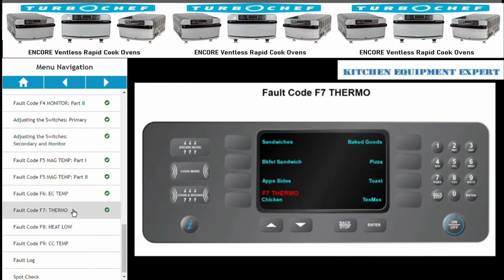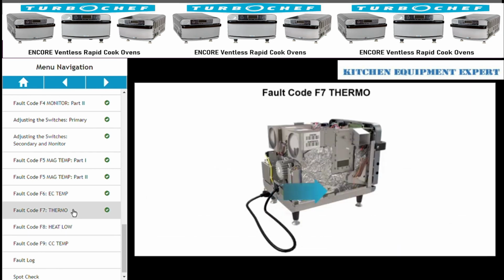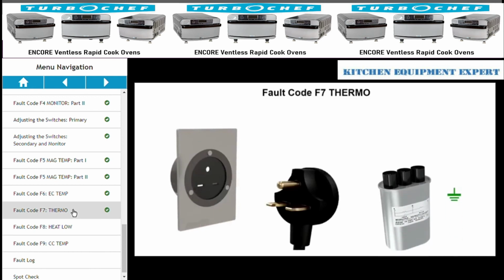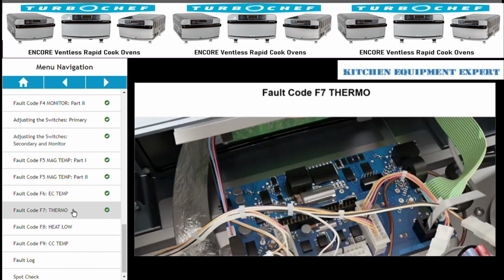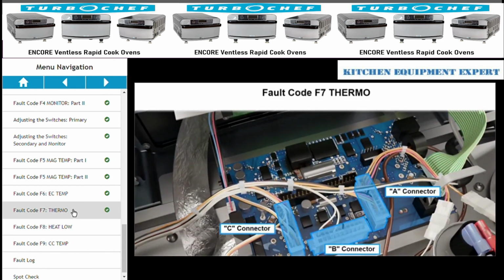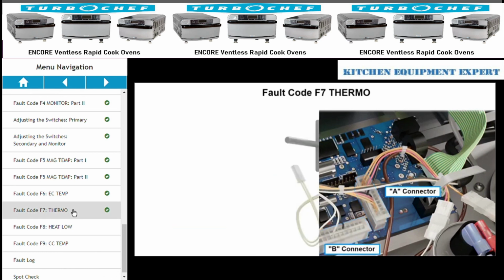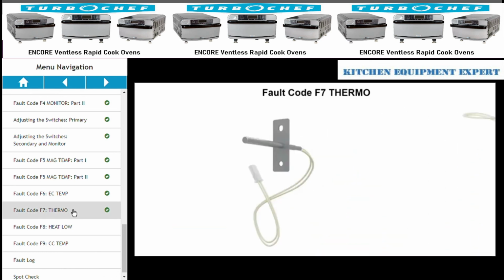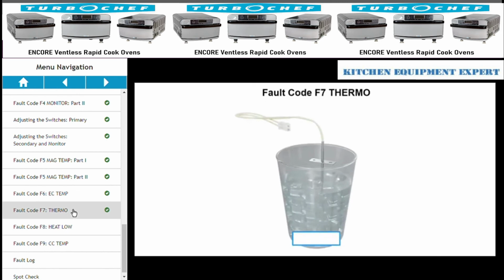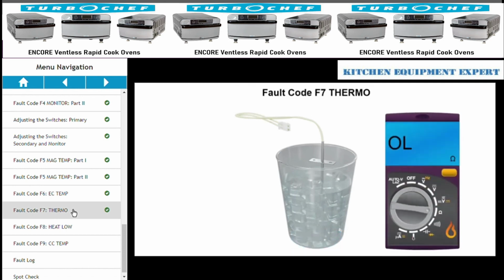The F7 fault code is triggered when the main control board has read the RTD as open. Unplug the oven and discharge the capacitors. Check the connectors at the main control board and at the RTD. If that seems okay, remove the RTD and test it by submersing the sensor in ice water for 2 minutes. At 32 degrees Fahrenheit, or 0 degrees Celsius, the RTD should have a resistance of 100 ohms. If the RTD reads infinite or open, replace it.